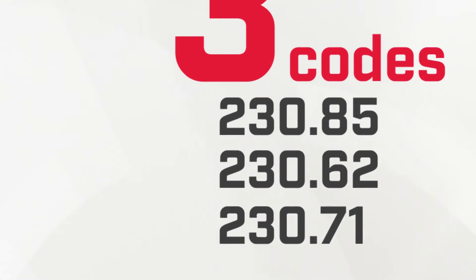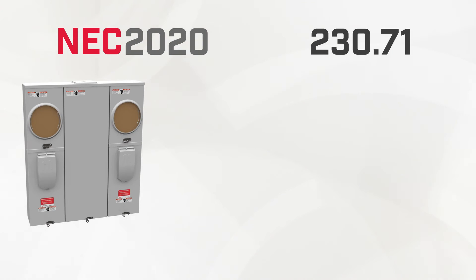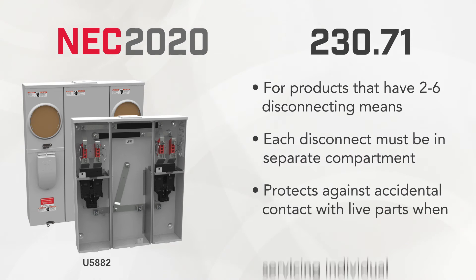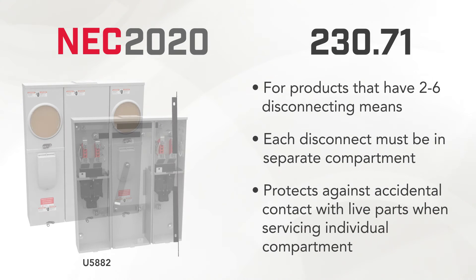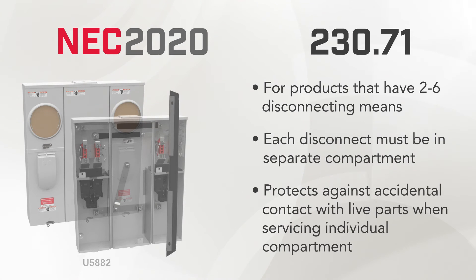The next code section that affects Milbank equipment is 230.71. This applies to products that have two to six disconnecting means. Code Section 230.71 allows for two to six disconnecting means when each of the disconnects is in a separate compartment. This change provides protection from incidental contact with live parts when servicing an individual compartment. Milbank has made changes to multi-position meter mains by adding a barrier between each of the disconnects, separating each one into its own compartment.